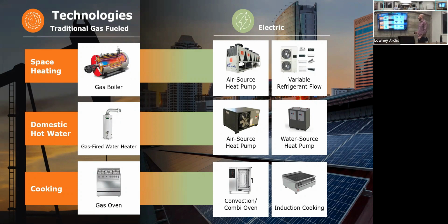ovens or stoves. So what we will be seeing more and more, we already have variable refrigerant flow systems commonly used, but also in the last few years we are designing buildings with air source heat pumps as the main heating element. So these are electric equipment that basically extract the heat from the outdoor air and then put it into your system and provide space heating using electricity. Domestic hot water heating, again, uses similar air source heat pumps, similar technologies, just with smaller dimensions that are specific for domestic hot water use rather than space heating.